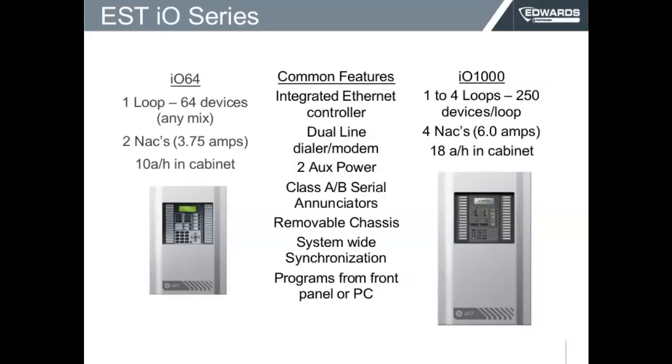The iO system is comprised of two panels. There's a smaller panel called the iO64. That panel has one loop with capacity of up to 64 devices on any mix. That means that you can have two detectors and the rest of the points could be modules, or you can have 10 modules and the rest of them will be detectors. It's not like the usual panel divided in half — in this you can mix and match.